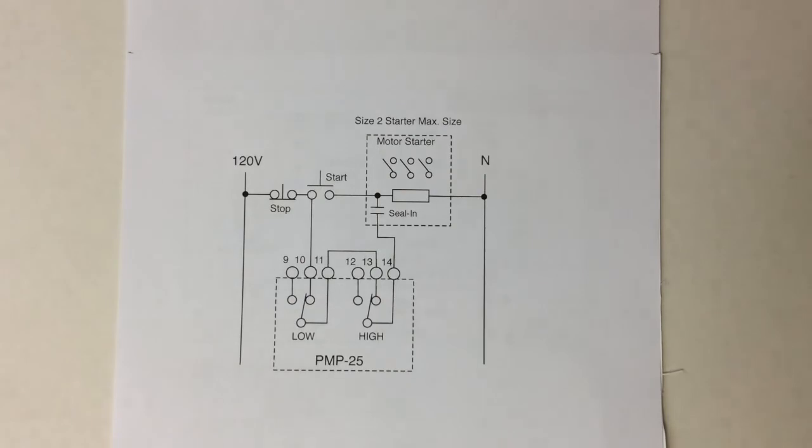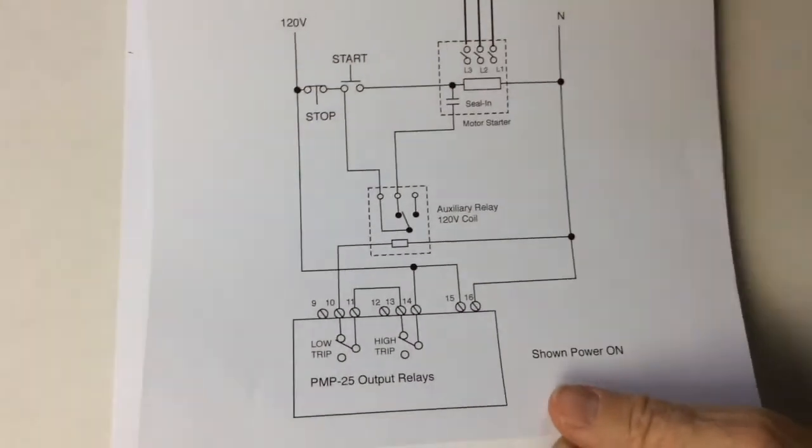The PMP25 output contacts can directly control size 1 and size 2 starters. For larger motor starters, an auxiliary relay must be used between the PMP25 and the motor stop circuit.